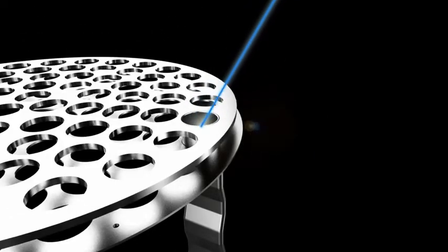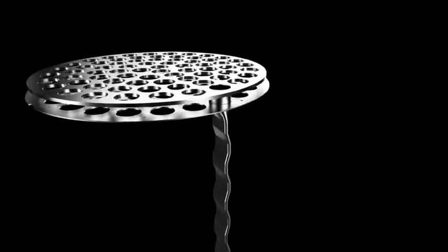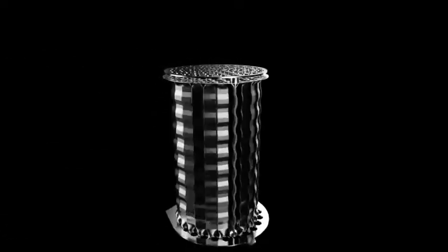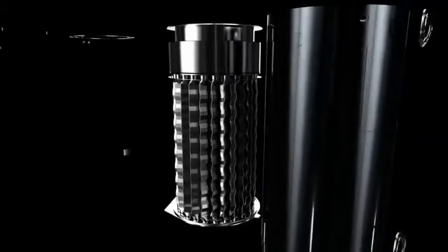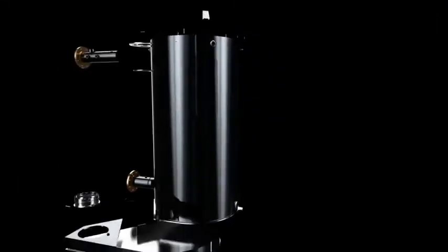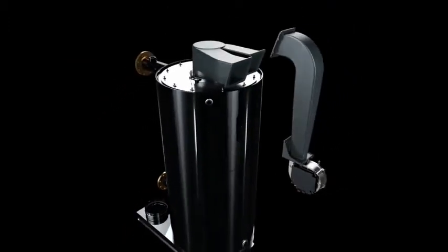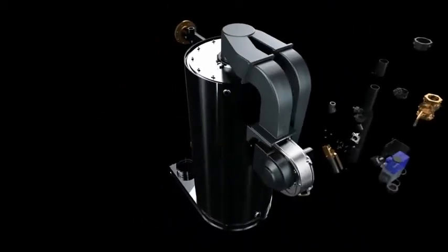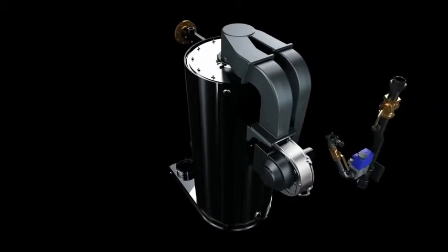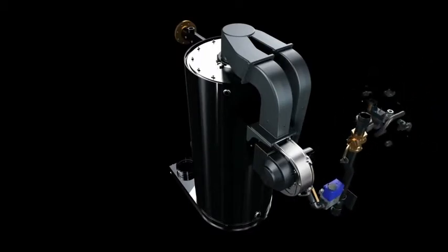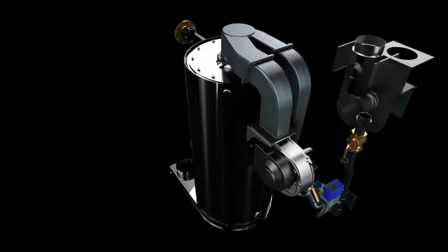It is inserted into the stainless steel top and bottom tube sheets and welded. Dozens of wave tubes are bundled to form the core of the CREST heat exchanger, completed by the combustion chamber, pressure vessel, water connections, and flue collector. The combustion system includes a dual input woven mesh burner, dual neg reg blowers, gas train, and a combined airbox for simplified air intake and combustion air venting.